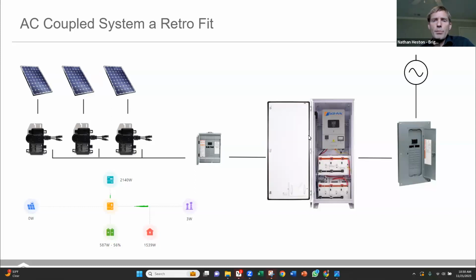What I'm showing you on the bottom left of the screen is the output of a real system. I pulled this off of one of our customers' system output earlier this morning. You can see the microinverter here from the Solarc is producing a couple of thousand watts this morning. There's battery power as well. This is an animated picture, so it doesn't really make sense as a still, but you can see the flow of that power. If you come in through the loads port on the inverter, then you would be directing some of that power from the solar array directly into loads, so you don't have monitoring capability through the Solarc, but those Enphase units come with monitoring as well. You just don't have everything in one place as you do if you come through the gen port.